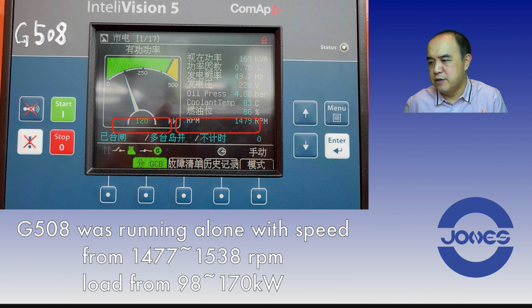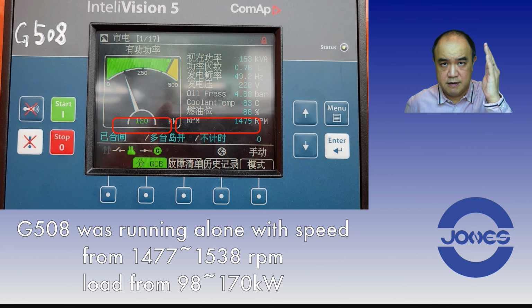So you can hear the engine was hunting. I was looking at it at this few seconds. It was going from 1477 to 1538 RPM back and forth. The load, of course, was going from 98 kilowatts to 170 kilowatts. We can't change the load. This is how the factory uses the load. The load fluctuates. It fluctuates a lot. Thereby, the speed would follow.